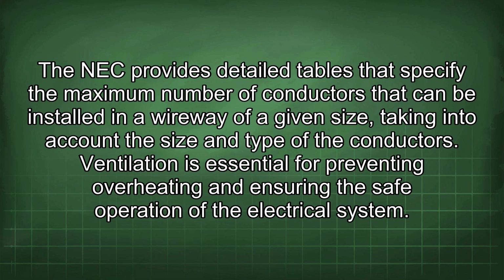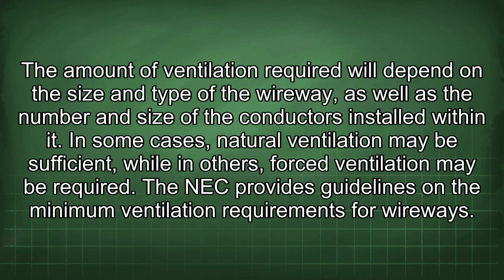Ventilation is essential for preventing overheating and ensuring the safe operation of the electrical system. The amount of ventilation required will depend on the size and type of the wireway, as well as the number and size of the conductors installed within it. In some cases, natural ventilation may be sufficient, while in others, forced ventilation may be required. The NEC provides guidelines on the minimum ventilation requirements for wireways.